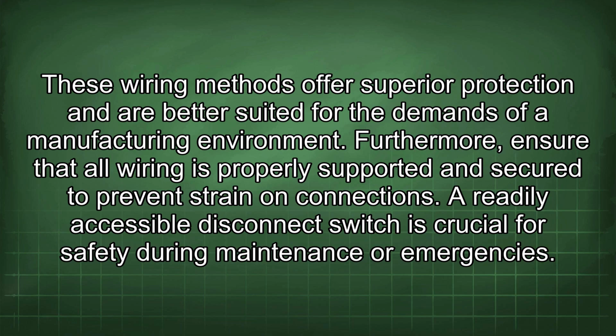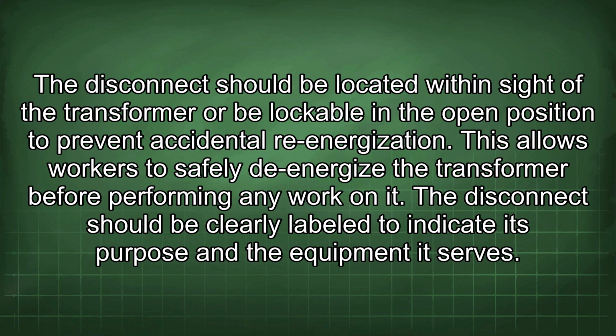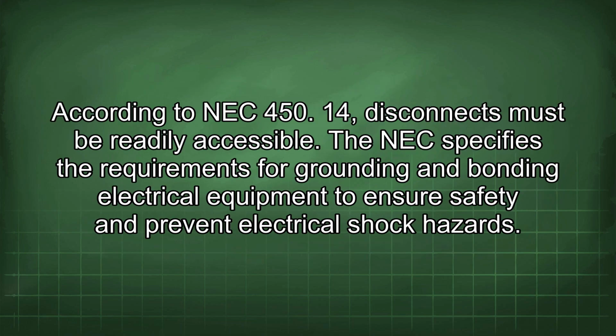A readily accessible disconnect switch is crucial for safety during maintenance or emergencies. The disconnect should be located within sight of the transformer or be lockable in the open position to prevent accidental re-energization. This allows workers to safely de-energize the transformer before performing any work on it. The disconnect should be clearly labeled to indicate its purpose and the equipment it serves. According to NEC 450.14, disconnects must be readily accessible.